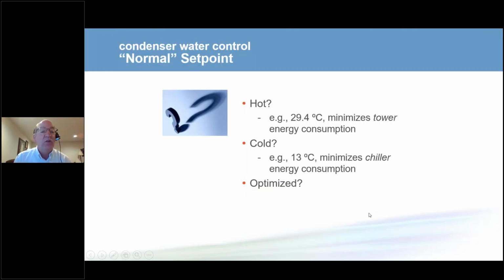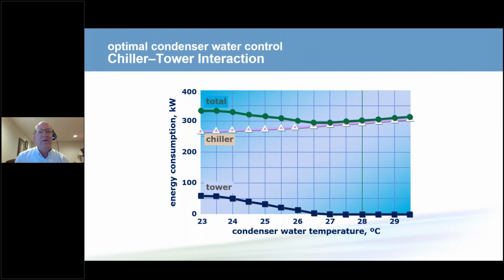Do we leave it at the design conditions of 29 or 30 degrees C? Do we drive the tower water temperature down to 13 degrees C when the wet bulb is lower? Do we optimize it? This is a graph of a chiller operating at part load condition, 60%, at a particular wet bulb temperature. At this wet bulb temperature, if we drive the cooling tower fans as hard as possible, the cooling tower can make 23.5 degrees C water temperature, and here's the chiller's energy usage. As we reduce the tower fan speed, its power goes down with about the cube of its speed. So as it goes to 26.5 degrees C leaving temperature, the chiller power goes up, but what we're looking for is where the sum of the chiller plus cooling tower energy is at its minimum.